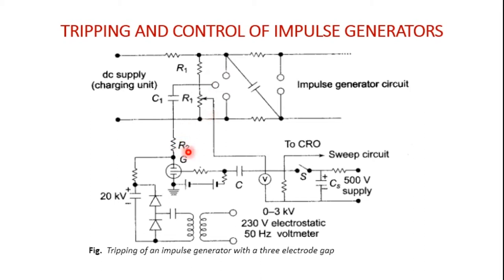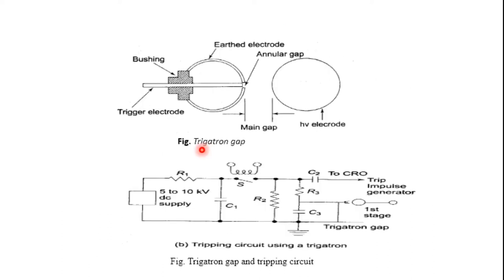R2 ensures decoupling of the voltage oscillations produced at the spark gaps from entering the oscilloscope through the common trip circuit. The three electrode gap arrangement requires large space and elaborate construction, so nowadays the trigatron gap arrangement is used instead, which eliminates the drawbacks of the three electrode gap arrangement.